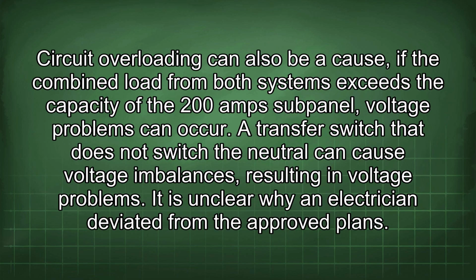Circuit overloading can also be a cause if the combined load from both systems exceeds the capacity of the 200 amp subpanel. Voltage problems can occur. A transfer switch that does not switch the neutral can cause voltage imbalances, resulting in voltage problems.